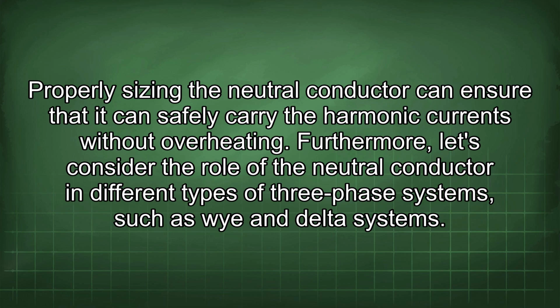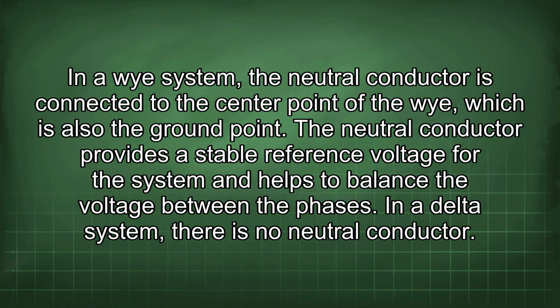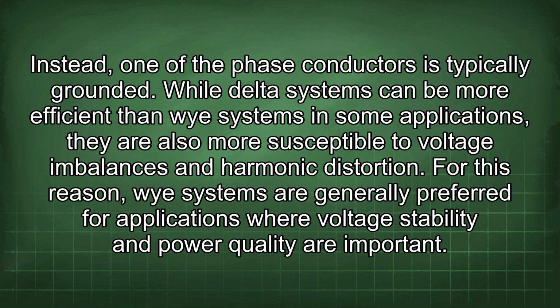Furthermore, let's consider the role of the neutral conductor in different types of three-phase systems, such as Y and delta systems. In a Y system, the neutral conductor is connected to the center point of the Y, which is also the ground point. The neutral conductor provides a stable reference voltage for the system and helps to balance the voltage between the phases. In a delta system, there is no neutral conductor. Instead, one of the phase conductors is typically grounded. While delta systems can be more efficient than Y systems in some applications, they are also more susceptible to voltage imbalances and harmonic distortion. For this reason, Y systems are generally preferred for applications where voltage stability and power quality are important.